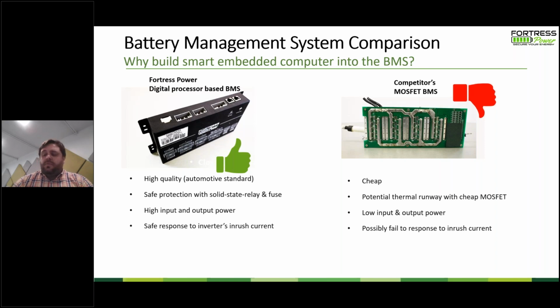Or you get batteries that are at different voltage levels. Maybe the installer didn't check how full each battery was during commissioning and commissioned the batteries at different power levels. You start to get battery to battery backfeeding. When you have three 100 amp batteries and two are backfeeding one, your individual battery is beyond the capability of the MOSFET BMS, and that burns up.